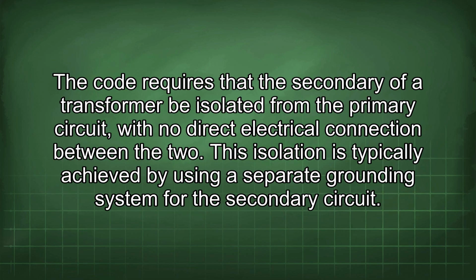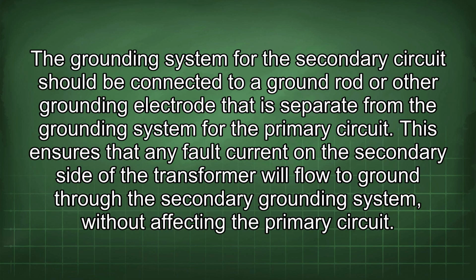The code requires that the secondary of a transformer be isolated from the primary circuit, with no direct electrical connection between the two. This isolation is typically achieved by using a separate grounding system for the secondary circuit. The grounding system for the secondary circuit should be connected to a ground rod or other grounding electrode that is separate from the grounding system for the primary circuit.